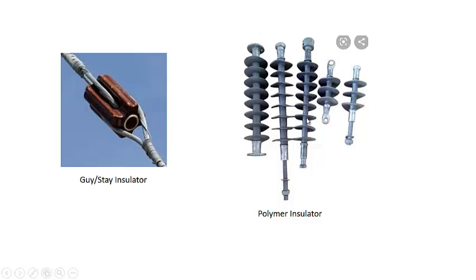So you can see pictures of the polymer insulators. You can see these petticoats are made of polymer, or rubber, just to increase the creepage distance, and the metal rod is made of glass fibers to increase the tensile strength and also the dielectric strength.